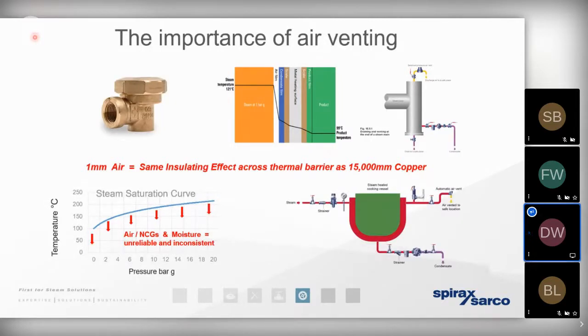And the reasons are primarily, one, an excess of air can create corrosion of the steam distribution network itself. But an even bigger problem is the fact that any film of air can be a significant barrier to heat exchange. It's got an insulating effect, as you can see demonstrated in the middle of the screen here. But that insulating effect also means that we are then no longer able to rely on that pressure to temperature relationship to break down the energy that passes into the process. So we always encourage you to utilize a thermostatic air vent, both at the process and at the very, very end of the distribution pipework, to allow the air to be passed away from the network. So we always refer to air venting as a completely separate issue, but at the same time as steam trapping.